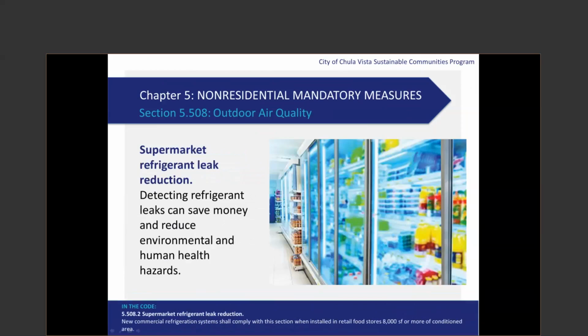More importantly, to prevent ozone depletion, this measure requires a number of steps to reduce refrigerant leaks in retail refrigeration equipment. Requirements include compliant piping and installation that allows for leak detection and repair. Components included are valves, tethers, piping, and evacuation. It's pretty detailed, but specific to supermarket refrigerant leaks.